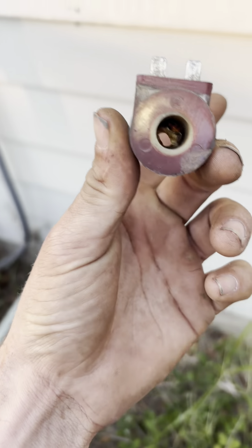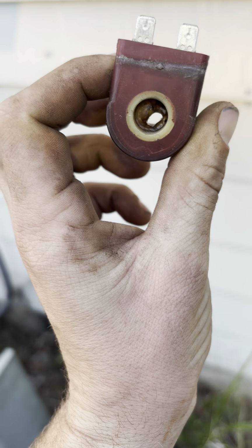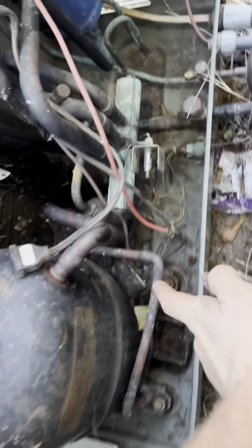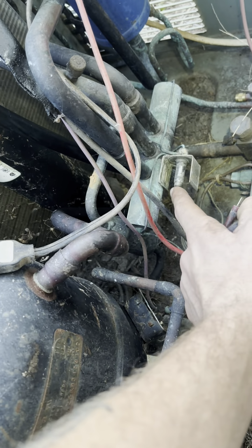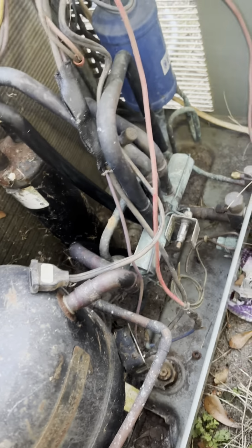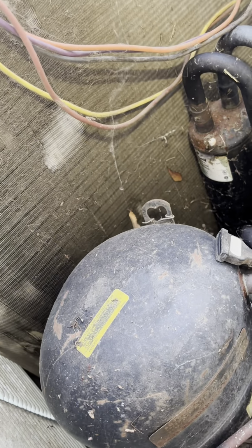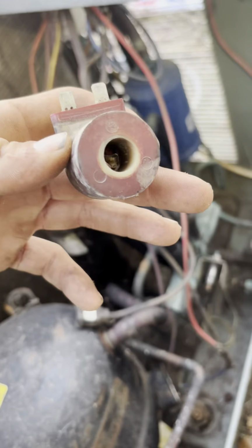All right, right now it's running cool. Found the problem. It is melted shut, the solenoid. This solenoid right here is supposed to go on this, and that switches the flow of refrigerant and makes it heat instead of cool. So this will be cold out here and the one inside will be hot. So I've got to go find another one of these and figure out why that happened.